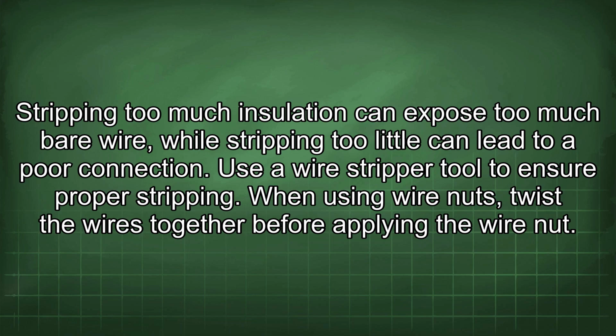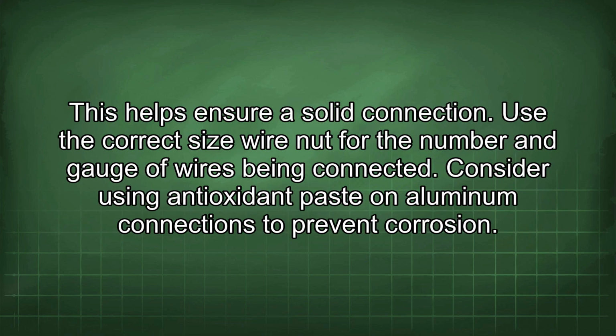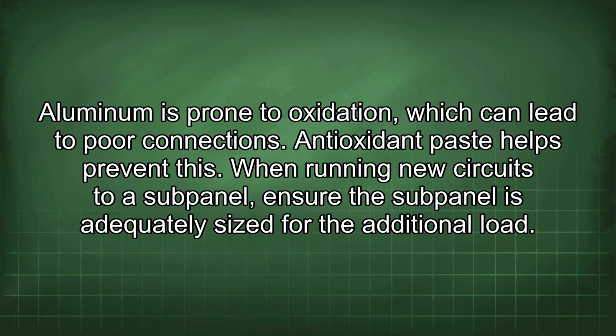When using wire nuts, twist the wires together before applying the wire nut. This helps ensure a solid connection. Use the correct size wire nut for the number and gauge of wires being connected. Consider using antioxidant paste on aluminum connections to prevent corrosion. Aluminum is prone to oxidation, which can lead to poor connections. Antioxidant paste helps prevent this.